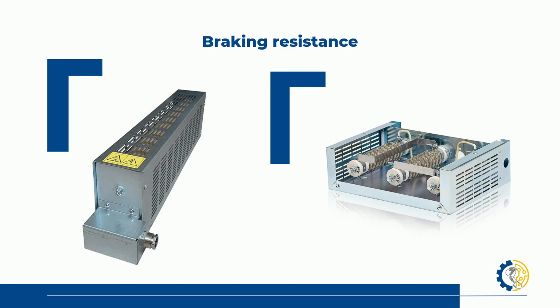Now, this drawing looks very good, very refined. But at the moment when we exceed our inertia, we generate an excessive amount of energy. And the only thing that our brake resistance does is take that created or generated energy, store it, and dissipate it through resistance. That's basically it.